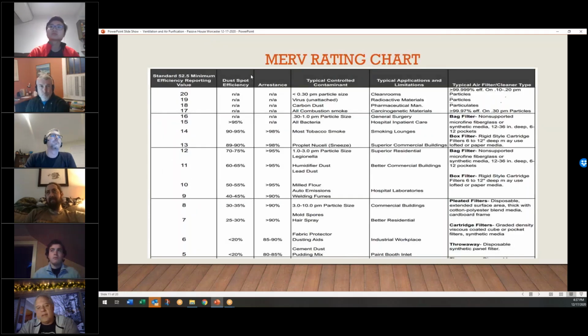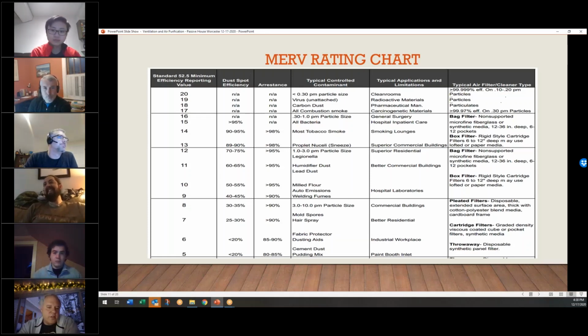What do we got? Next slide is, okay, so this is right out of ASHRAE. Most filters up until this year, MERV 8 was kind of a common, good quality filter, or used to be considered a 30% filter, common in commercial buildings. Since the pandemic, ASHRAE has gone to recommending MERV 13. You can see it's a much higher level, from 30% to basically 90% efficiency. So it does make a huge difference.